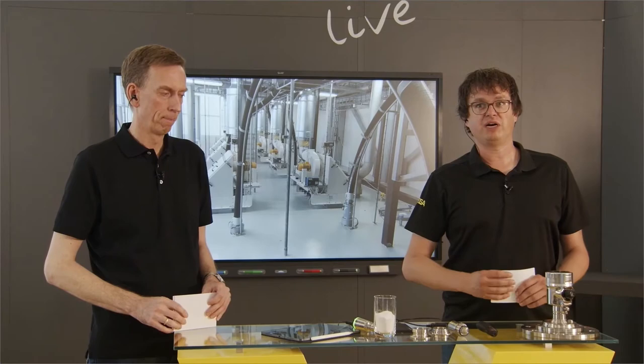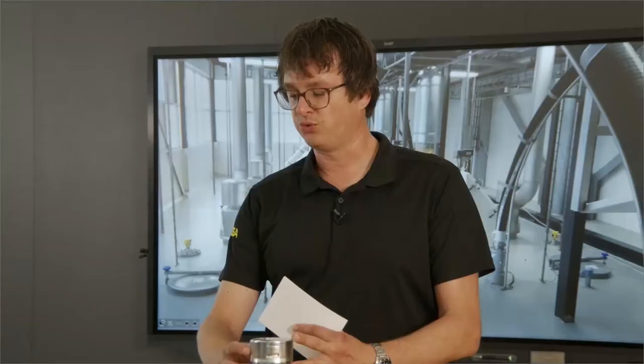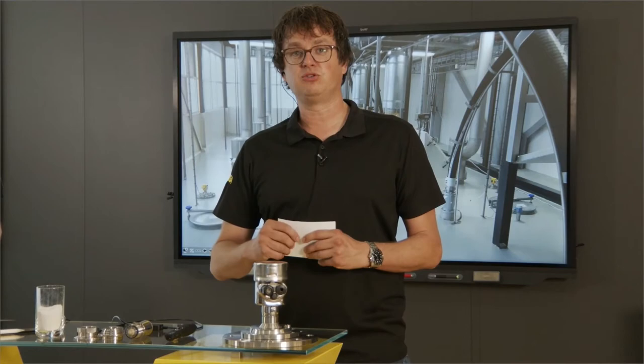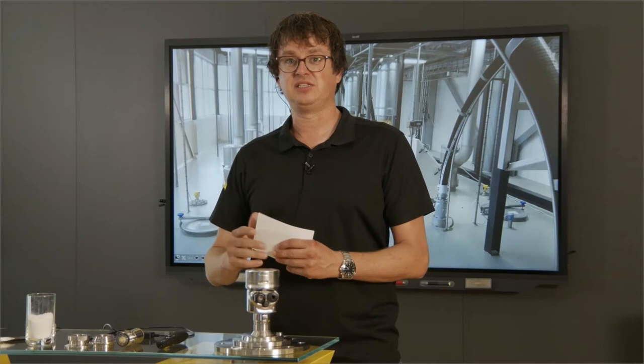We started with level measurements 15 years ago and after five or six years we saw it was getting more and more difficult for the first sensors to distinguish a product echo from background. At that time we developed a new electronic insert with a higher dynamic range, and with that we were able to create a reliable measurement with the same device. But with continuous development at Friesland Campina even that didn't work anymore, so we installed the new VEGAPULS 69 — the 80 GHz radar sensor with an even higher dynamic range — and since then the level measurement has been working fine without any big problems.